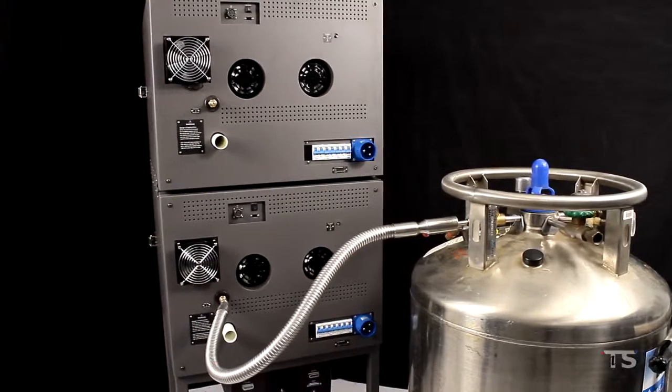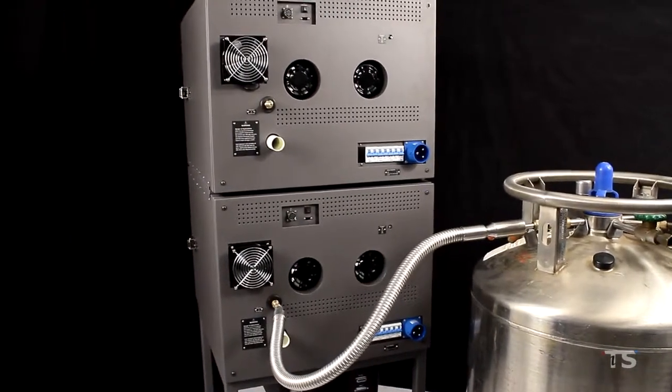Hand tightening the connections at the Dewar and thermal chamber will minimize the chance of cross-threading these connections.